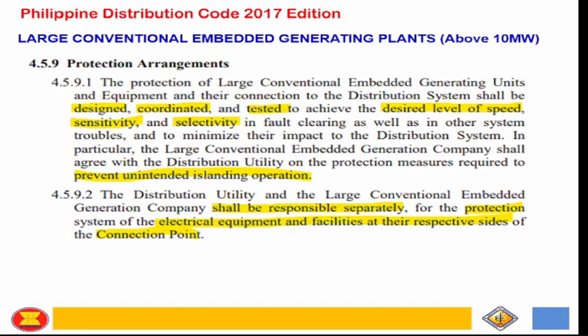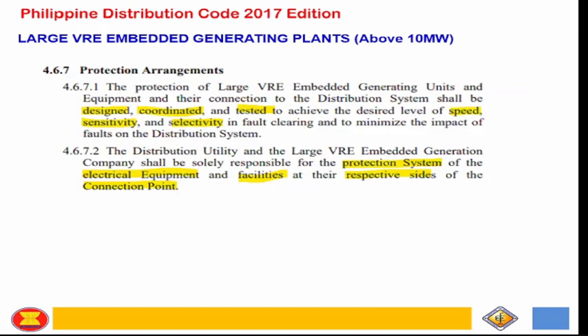So that's the provision. They shall be responsible separately for protecting the electrical equipment and facilities on their respective side. The DU is responsible for the distribution utility side, and the embedded generator or DG is responsible for their own side. So any problem or damage there is the responsibility of both parties. And for the large embedded generating plant, the provision is the same: designed, coordinated, and tested to achieve the desired level of sensitivity and selectivity, on their respective side.